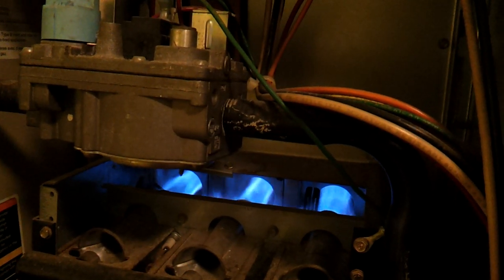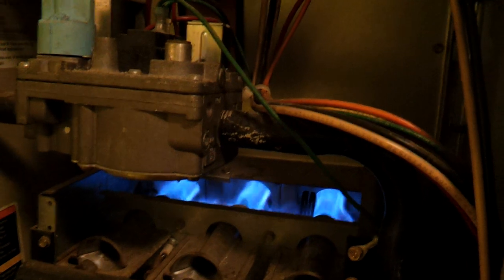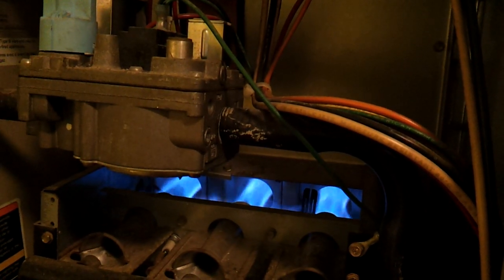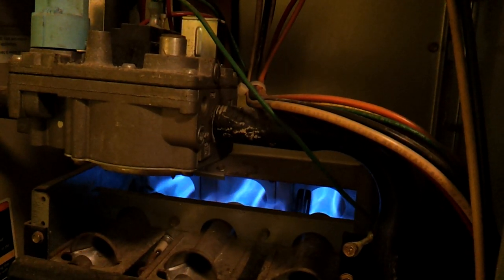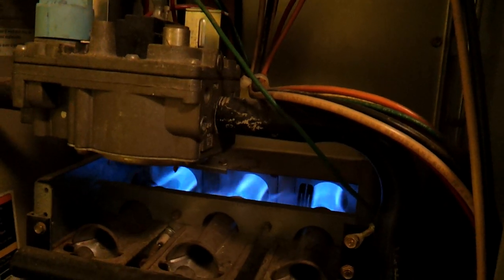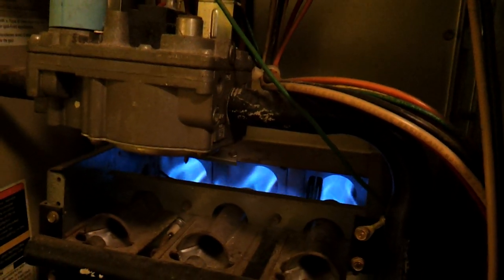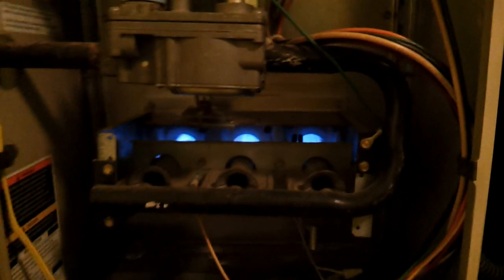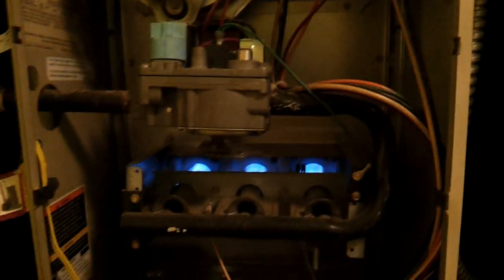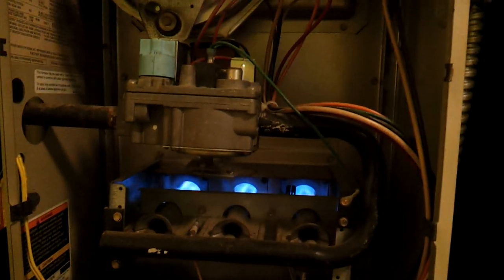And as you can see, after the blower came on, the flames did not really change in appearance, which means that the heat exchanger is good. Probably doesn't have any cracks in it. Oh, and also back in there, I don't know if you can see it behind the gas valve, is a high limit switch, so if that trips, it'll also shut down the unit. So, you know, pretty standard gas furnace, got all the safeties in it.